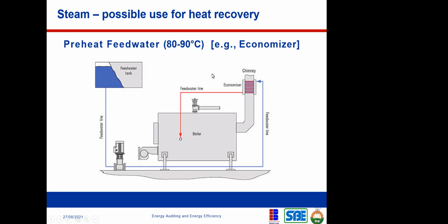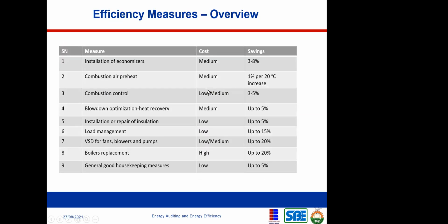So that's what we mean by economizer. Okay, so let me come back to this place. So you can actually save between 3 to 8% by doing that. So combustion air preheat. Now, what this is saying is that before, when you're doing your combustion, it's a combination of oxygen, right? So if you also preheat the air that you're injecting into your boiler, it's also going to improve the efficiency of your boiler.